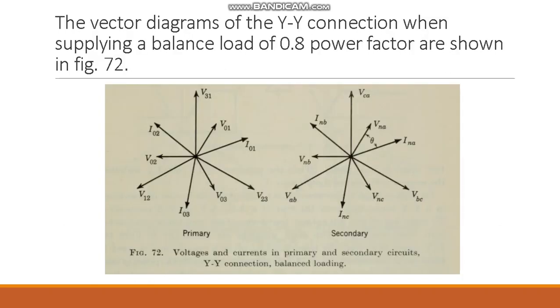The effects described may also occur to a smaller degree when the secondary is used to supply an unbalanced three-phase load from points A, B, C. The unbalance in these cases results in the difference in the magnitude of the impedance drops in the individual transformers. The Y-Y connection is only recommended on balanced loads, as shown in the vector diagram of Y-Y connection when supplying a balanced load of 0.8 power factor.